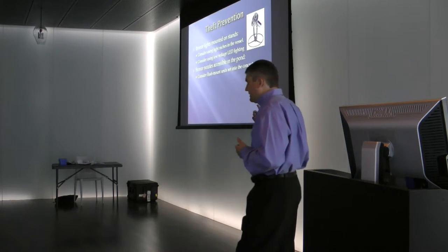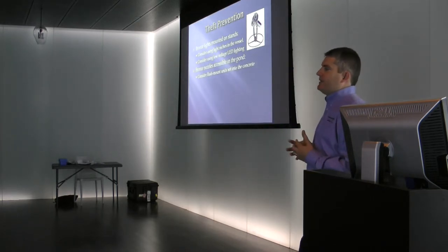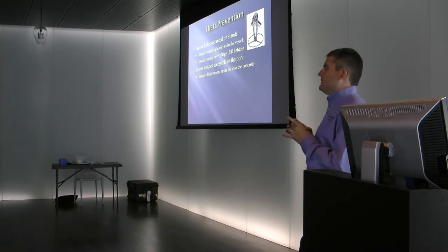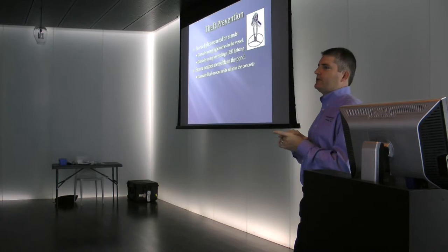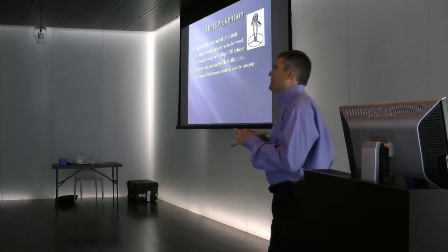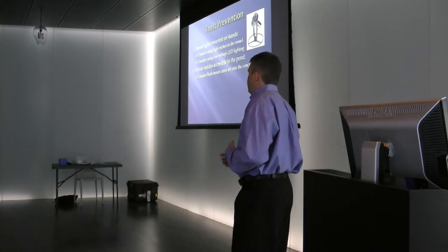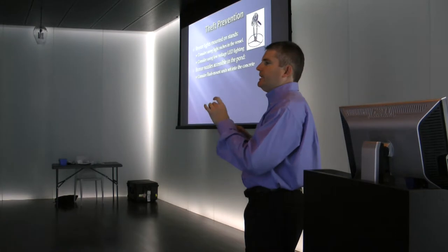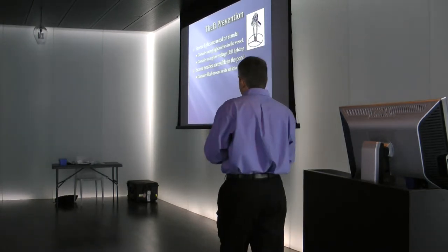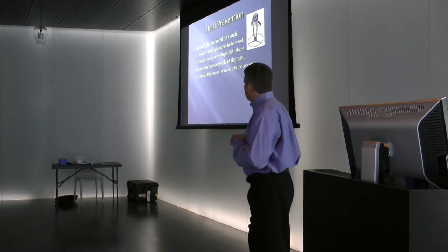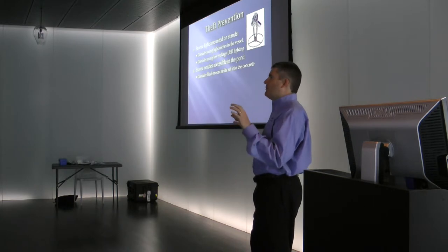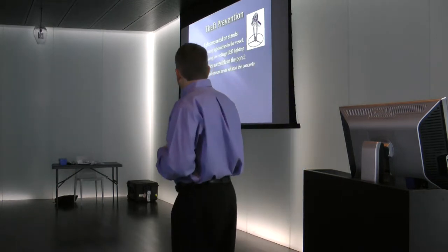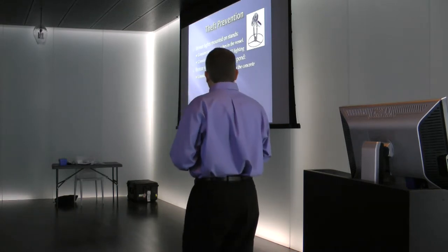Also, kind of new technology, LED lighting. The colors are getting better. They've got warmer colors now. Things aren't quite so blue. And the fixtures are getting really small, so small that you don't even really need a rock guard on them anymore. The code says that if you've got something in the floor, you need a rock guard over it so somebody doesn't step on it and break the glass and have their foot go through it. But these LED lights are getting so small, they fit in a 2-inch or 1.5-inch conduit, and you just don't need those big bronze rock guards anymore. They're also easier to install in renovations because you can core through the walls and add these little lights, as opposed to getting a jackhammer out and breaking large holes and dealing with all the reinforcement. So that's another option that you may want to consider.